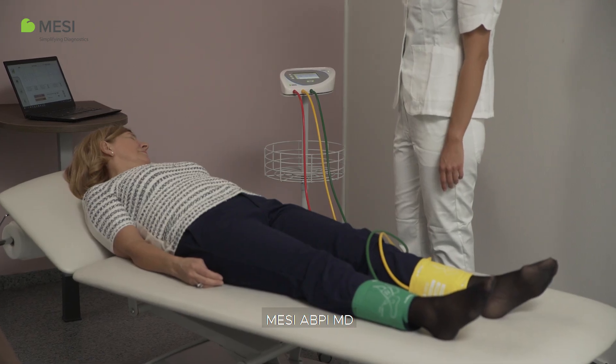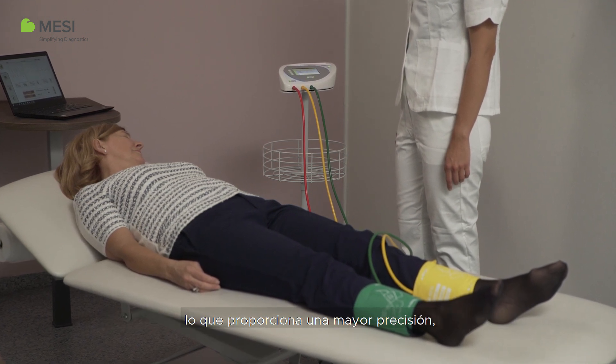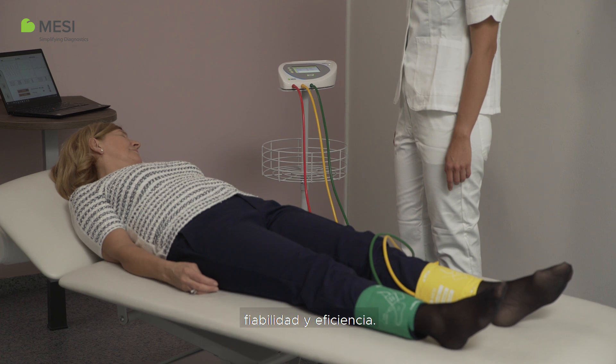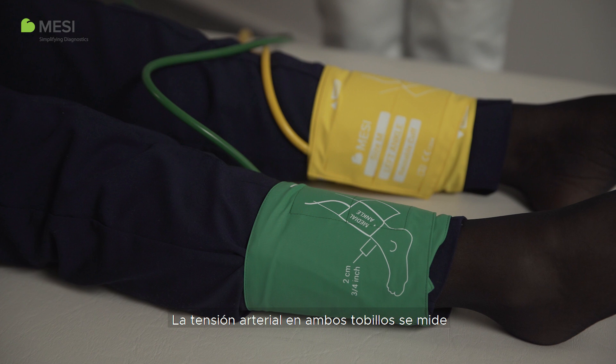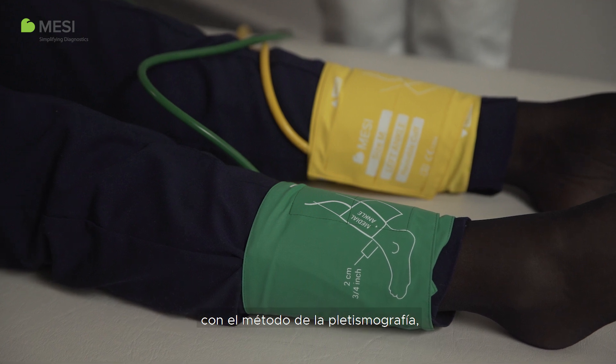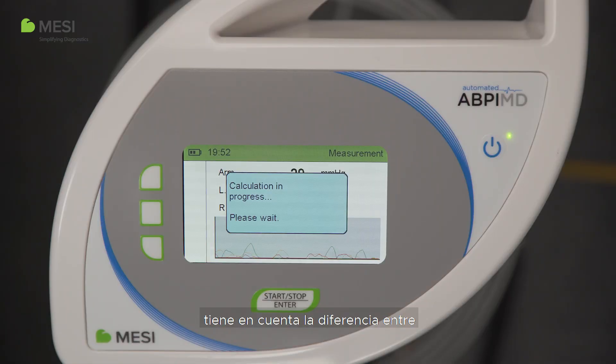The maximum pressure in the cuffs is calculated during inflation and therefore varies from person to person. The MESI ABPI-MD uses a unique three-cuff simultaneous measurement, which provides higher accuracy, reliability, and efficiency. The inflation and deflation of the cuffs is controlled by an algorithm. The blood pressures in both ankles are measured using the plethysmography method, which, in addition to its high sensitivity, takes the difference between arm and ankle anatomy into consideration.